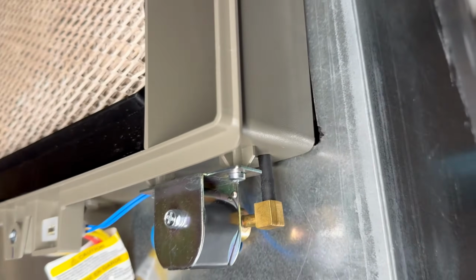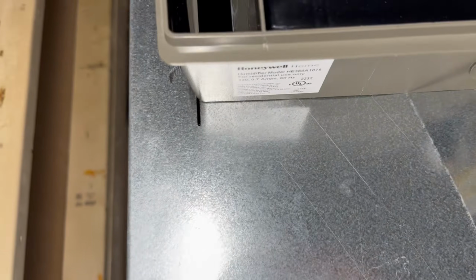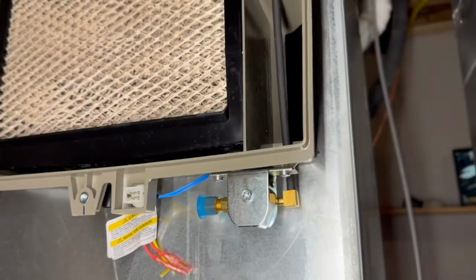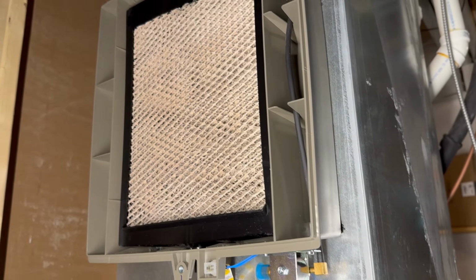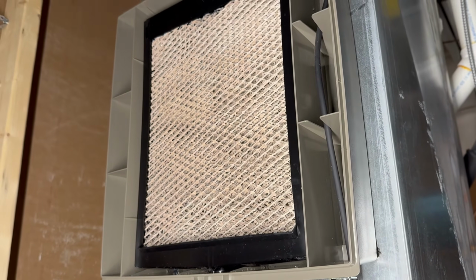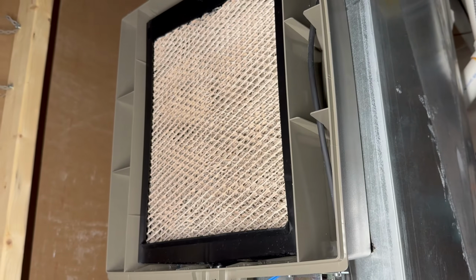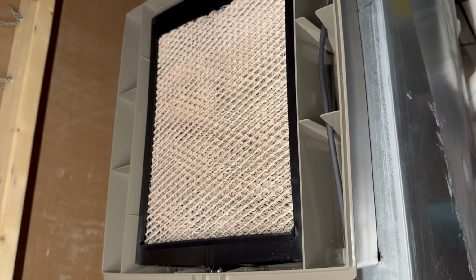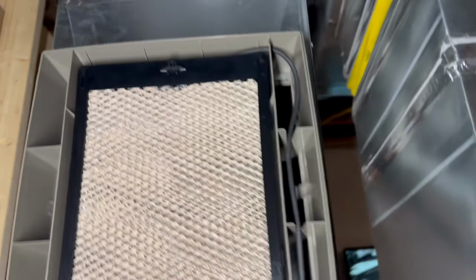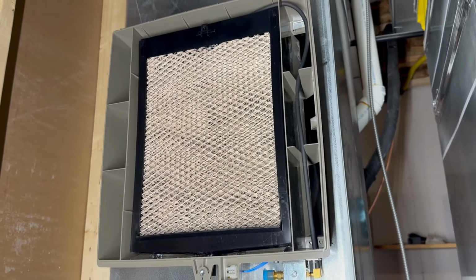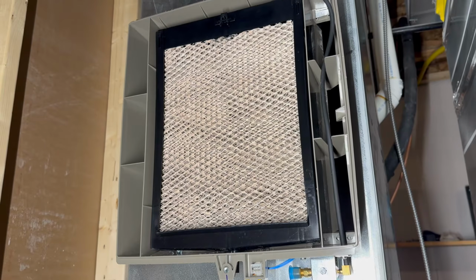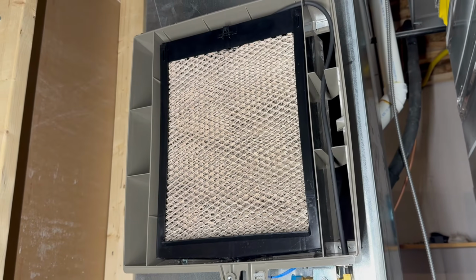Also notice that my cut is not perfect. You'll see here in that corner. So you want to ensure that you have no leaks. So you have two options. You can either tape it with aluminum HVAC tape, or you can get some clear HVAC silicone RTV, and you can RTV the entire surrounding of this unit, just so that you have a perfect seal and there's no air leakage from between the housing and the actual vent.